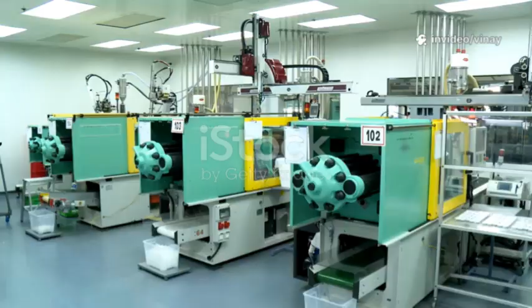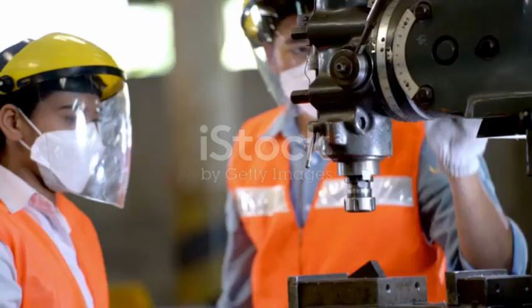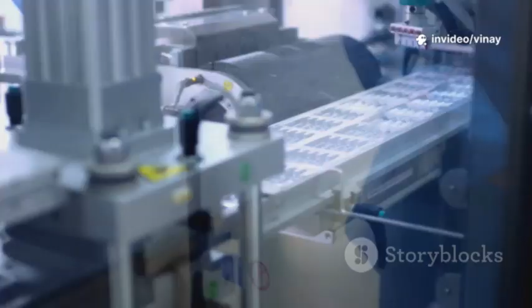Performance qualification, or PQ, is the ultimate test, proving the machine can consistently make a quality product under real conditions. The machine runs with actual materials, operated by trained staff, following standard procedures. Typically, at least 3 consecutive successful batches are produced and tested for key quality attributes. Consistency is key—the machine must deliver the same results, batch after batch.